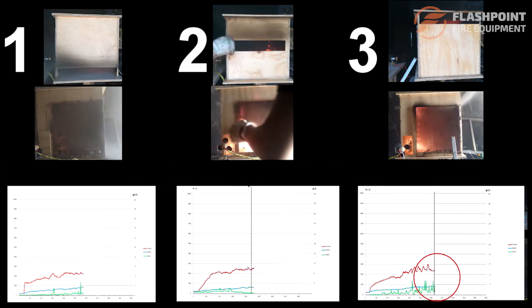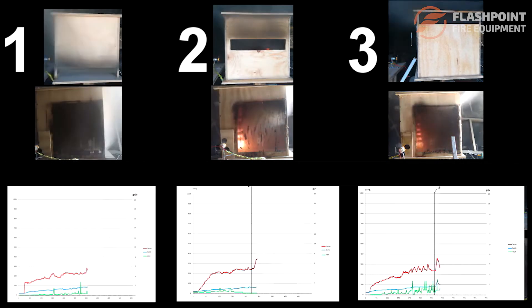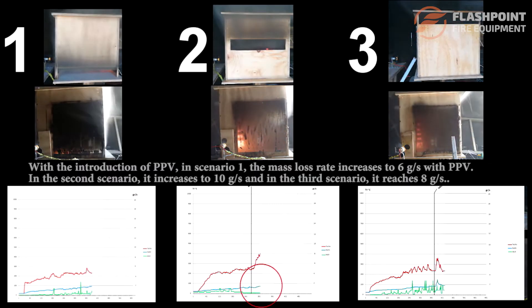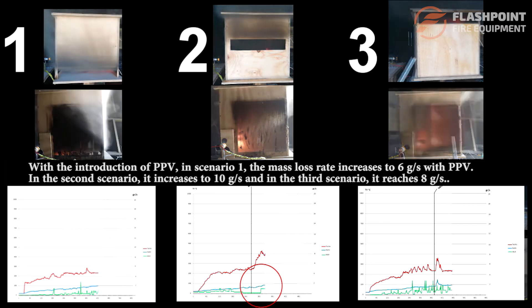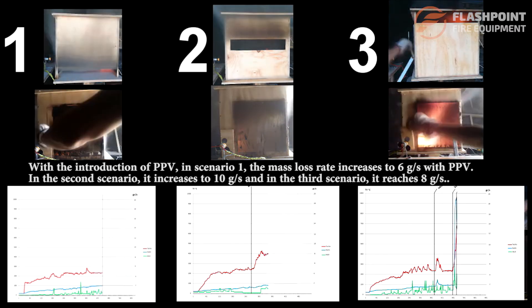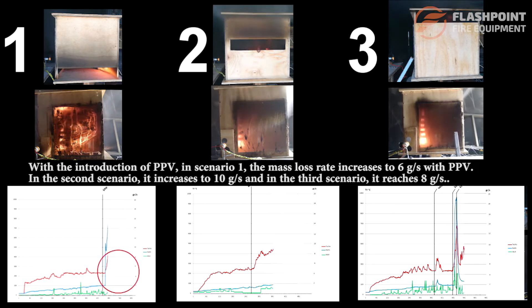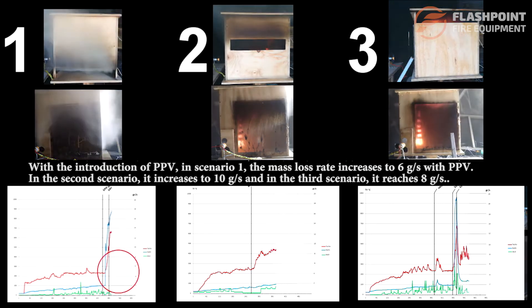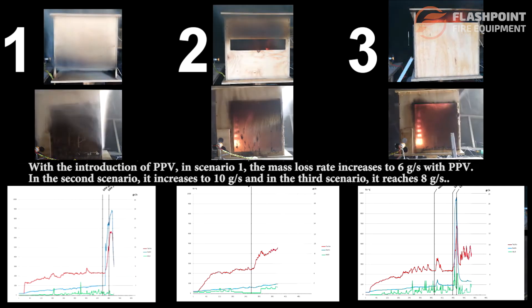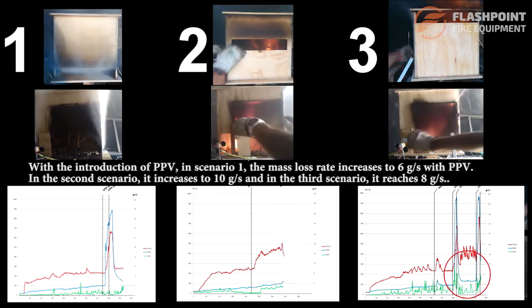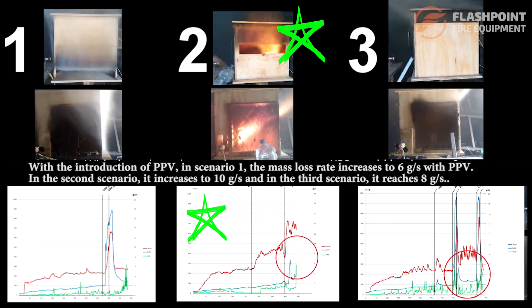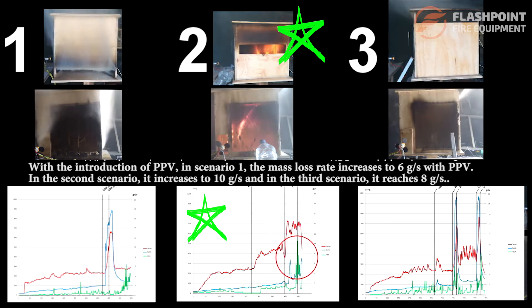Mass loss rate changes significantly with the introduction of positive pressure ventilation. In scenario 1, the mass loss rate increases to 6 grams per second with PPV. In the second scenario, it increases to 10 grams per second, and in the third scenario, it reaches 8 grams per second. Comparing scenarios 1 through 3, we can conclude that the heat release rate is highest in scenario 2, the horizontal opening at mid-compartment height.